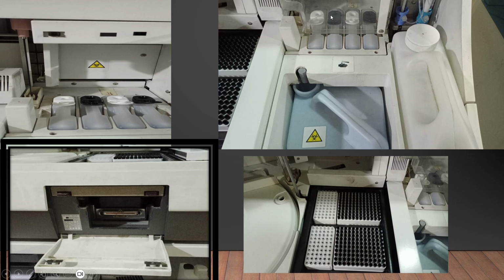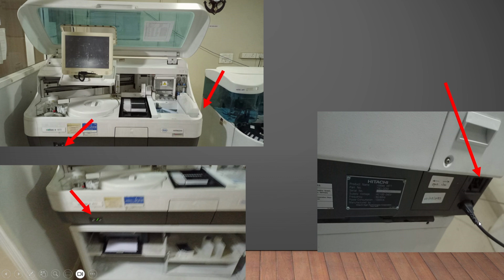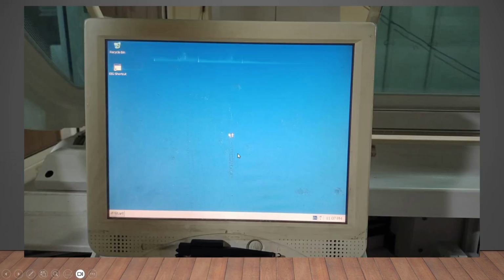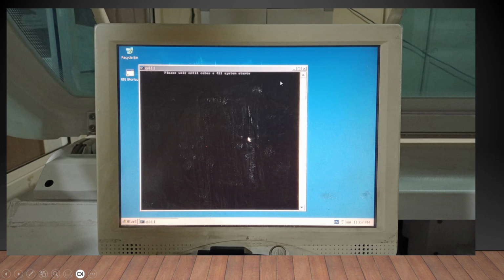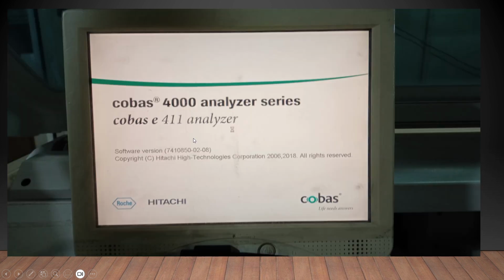Then you have to make sure that the ProCell CleanCell are kept, and the liquid level I have shown you. And this is the solid waste, so you have to remove it. All the solid waste, cups and tips, are removed, and the empty one is placed, and this door is locked. After all these things, you can place the reagent; it doesn't matter much when the instrument is started, right? Now after that, you switch on the power button, which is this. You switch it on, and then you switch on the analyzer. Immediately the CPU first switches on. After that, the Cobas software gets started. Then it will take a minute or two.